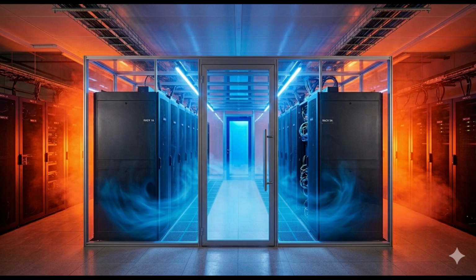But all of that is useless if the cold air doesn't actually get into the servers. Let's talk about airflow architecture, because the server rack isn't just a shelf. No, you have to look at the server rack as an active aerodynamic component. The servers have their own internal fans, they actively pull air, they generate a pressure difference across the rack, usually between 20 and 80 pascals. So the rack is basically an active flow channel. Exactly. The rack's airflow demand is totally proportional to the IT load.